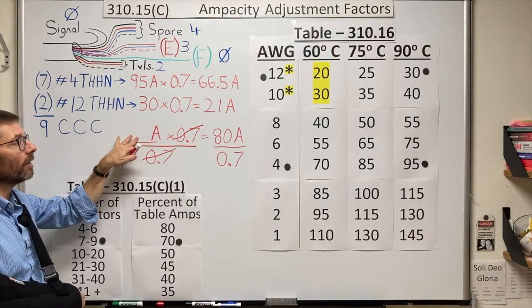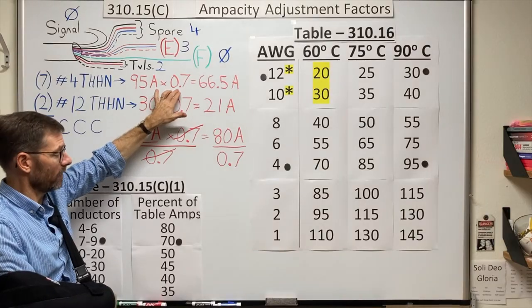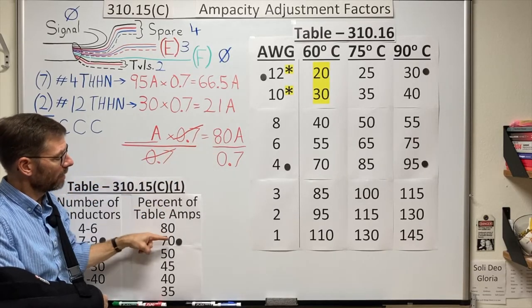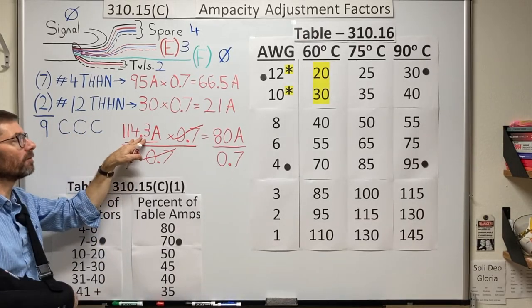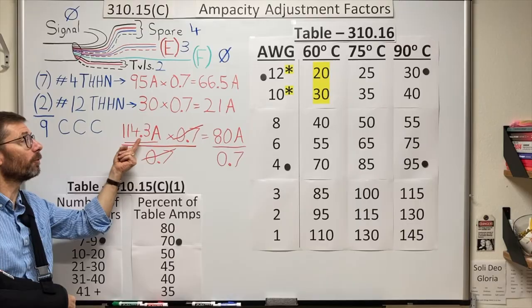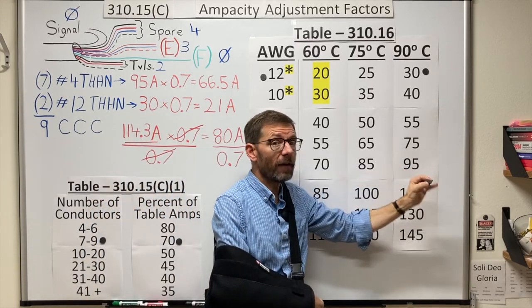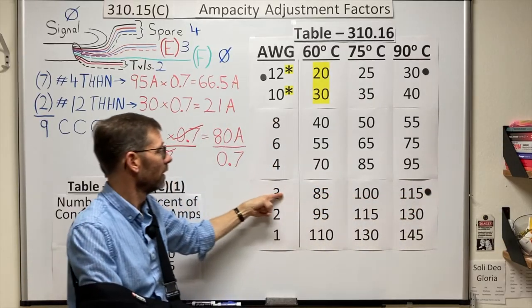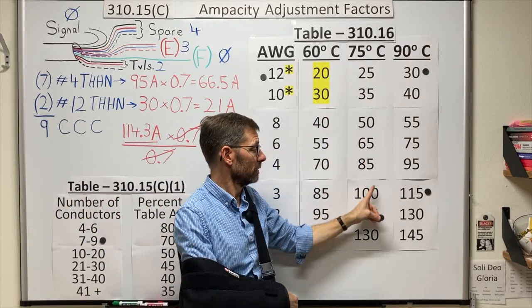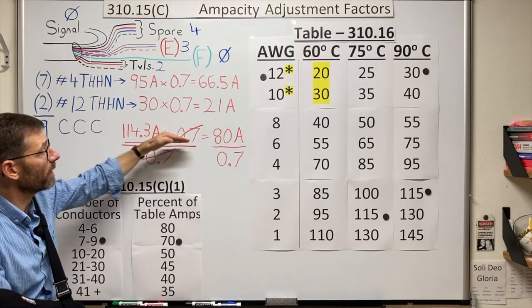So whereas the original way we took the conductor's ampacity times the factor from the table, here we take our desired outcome divided by the factor from the table to get 114.3 amps. That's the starting point. I need a conductor that can carry 114.3 amps at least before the derating. So a number four is not big enough. If I have a 90 degree conductor, I go down this column, that'll work. A number three would be adequate. Or if I had a 75 degree rated conductor, I would have to go up to a number two in order to have a large enough conductor. So you can choose which method suits your circumstances.